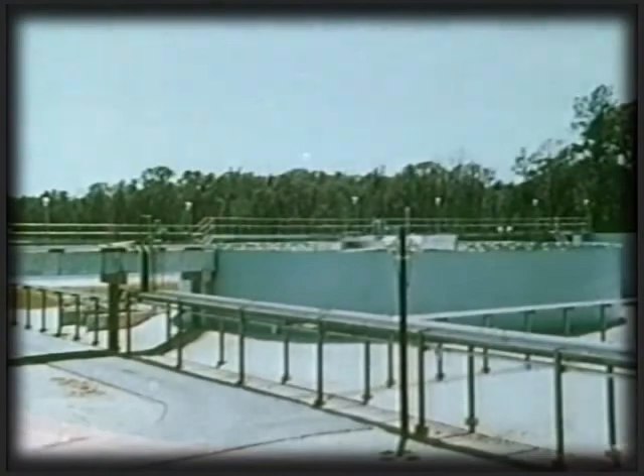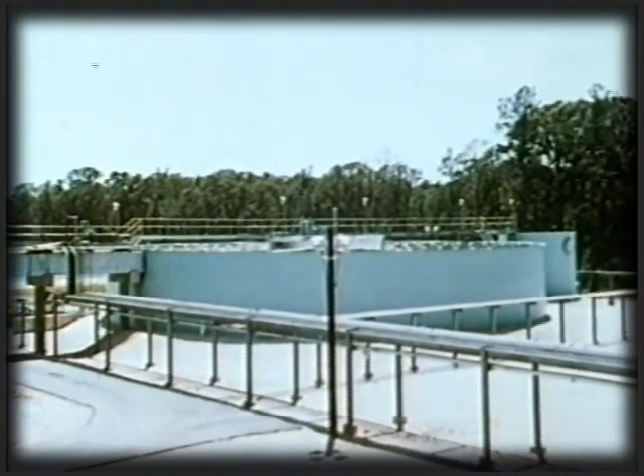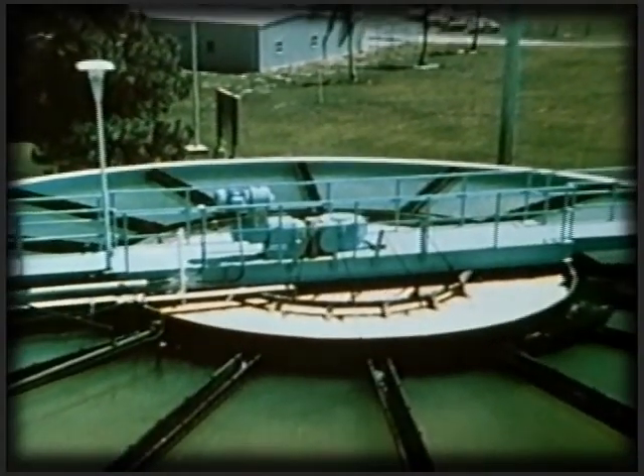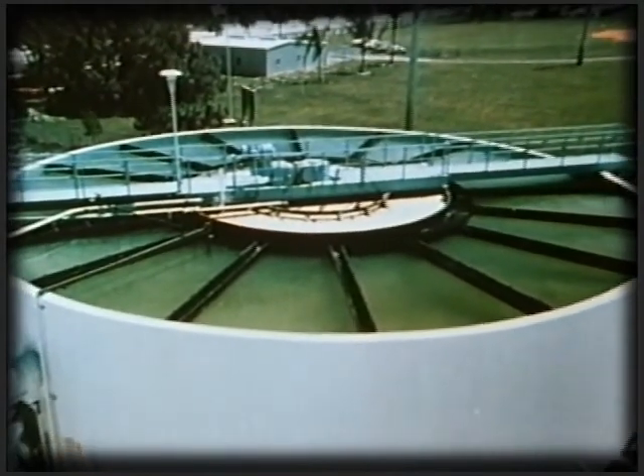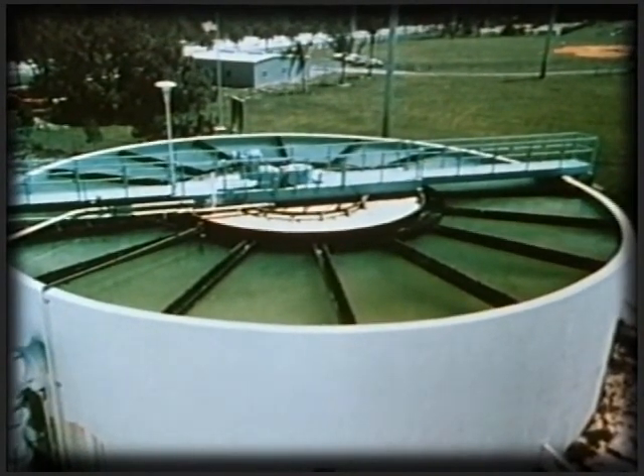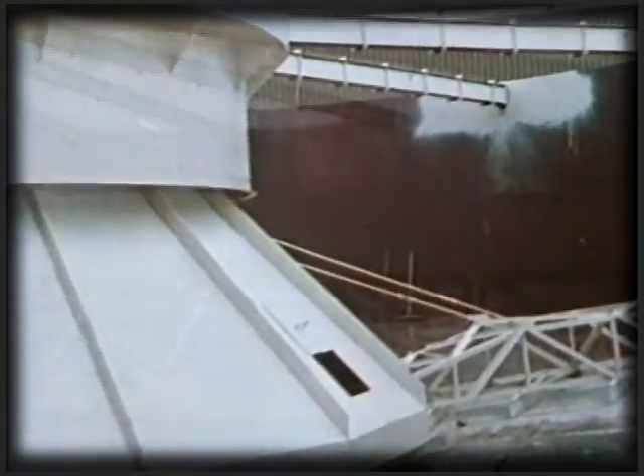Thousands of Accelators, both types NS and IS, are in operation today around the world, because they offer speedy mixing, flocculation, and precipitation in one compact unit. They are available for the complete range of basin sizes. Our NS Accelator is essentially similar in configuration to those demonstrated in this film. The IS Accelator differs in that it has the added effect of a bottom scraper, to assist in the efficient removal of sludge in larger basins.